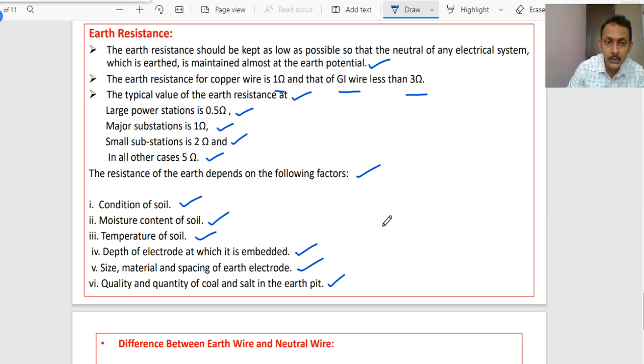All these factors, right, will decide the resistance of the earth pit or earthing system. So these factors are important. These are to be highlighted. What are those? Condition of soil, moisture content of soil, temperature of soil, depth of electrode at which it is embedded, size, material and spacing of earth electrode, and the quality and quantity of the coal and the salt in the earth pit will decide the resistance of the earthing system, right. So this is all about the earthing.